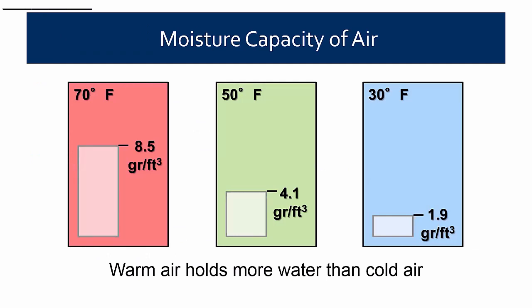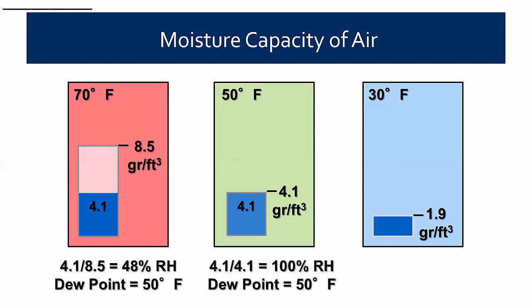This is a diagram showing moisture capacity. The one on the left is 70-degree air, 50-degree air in the center, and 30-degree air on the right. The capacity of 70-degree air to hold moisture is 8.5 grains per cubic foot — that's the amount of mass of water that air can hold. If we put in 4.1 grains of moisture, then the relative humidity is the ratio of the amount in the air versus the amount it can hold — so in this case, for 70-degree air, it's 4.1 divided by 8.5, which is 48%.